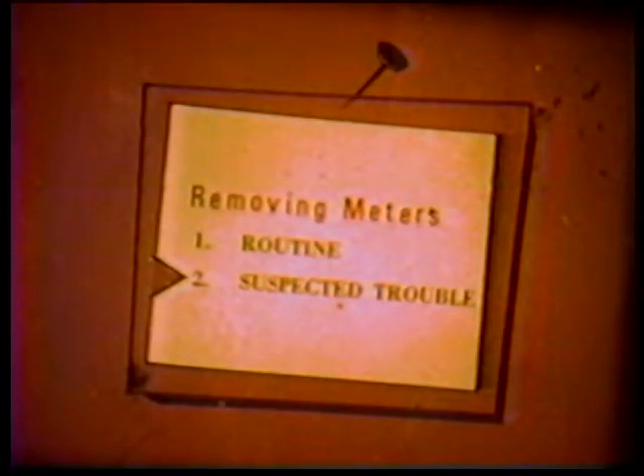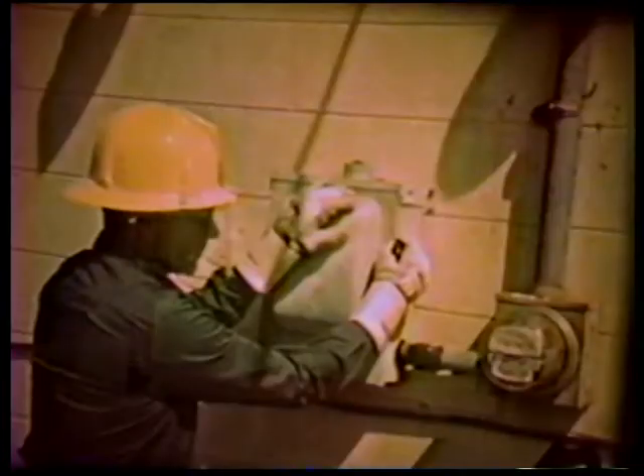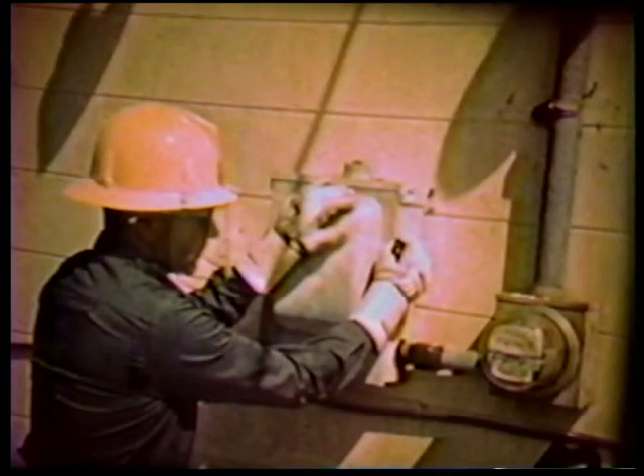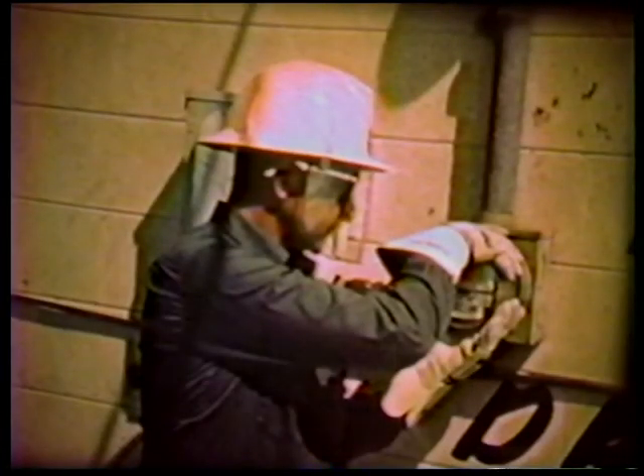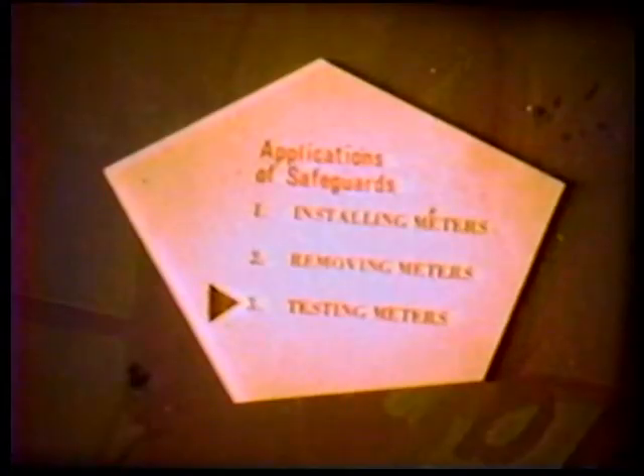When meters are removed where trouble is suspected, the same general procedure as outlined above should be followed, except power should always be switched off the meter circuit. Complete personal protective equipment should be used, including hard hat, face shield, gloves, and long-sleeve shirt buttoned at the wrist.